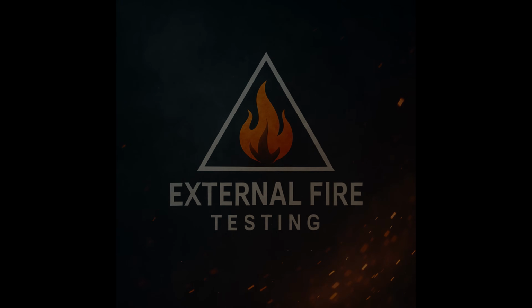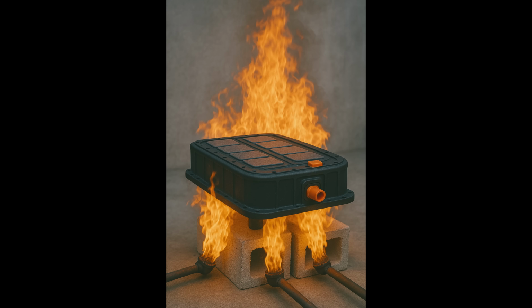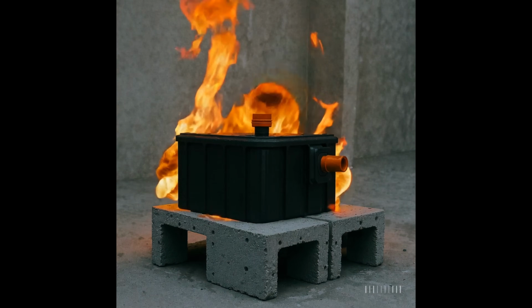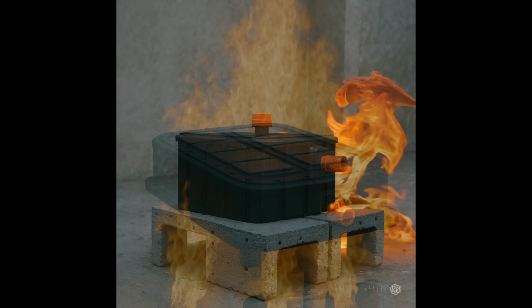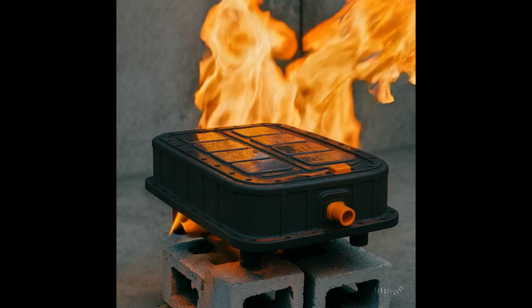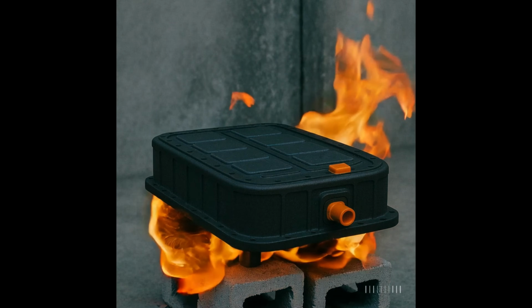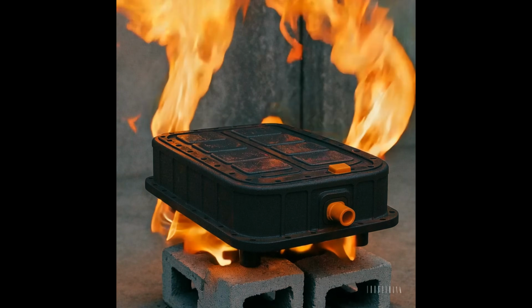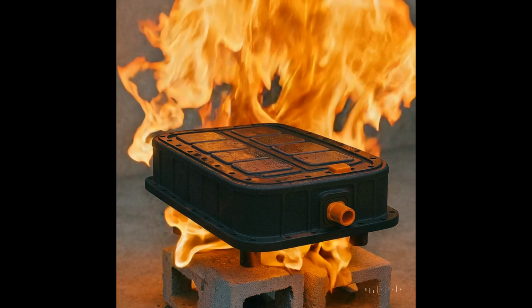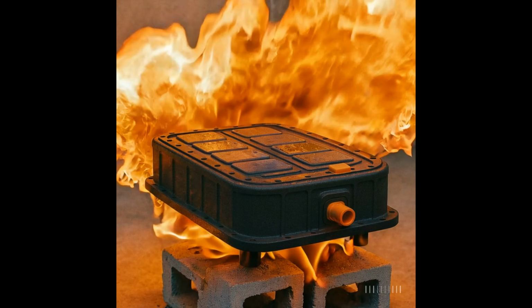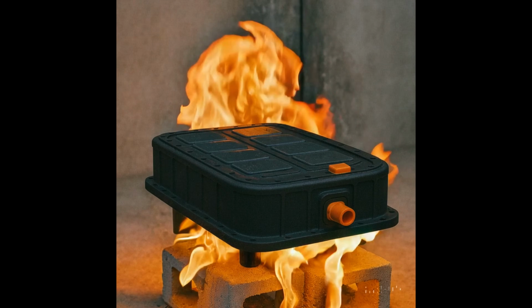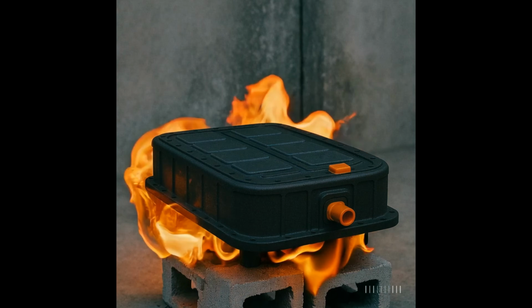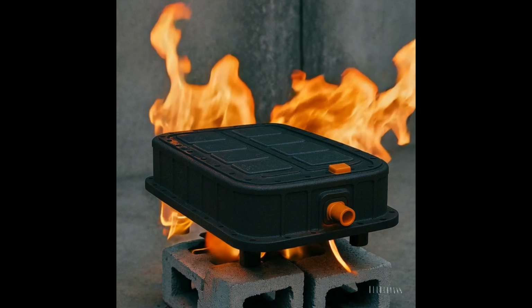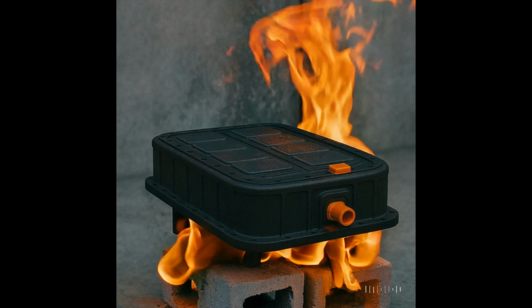External fire testing simulates real-world fire exposure from sources external to the battery pack. This test is used to determine how long the battery can resist thermal propagation and runaway, whether the pack undergoes violent rupture, thermal runaway, or cell venting, and the effectiveness of passive fire containment design of the battery pack. Implementation of the flame depends on the standard. However, a lot of standards include fuel fire, which is when a battery is placed over a pool fire, commonly gasoline or propane, for 70 seconds to 10 minutes, depending on pack size and standard. Typically, the flame exposure occurs horizontally or directly below the battery pack, but sometimes at an angle for corner exposure tests, depending on your requirements.